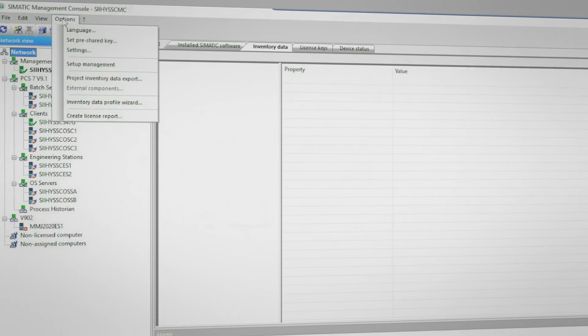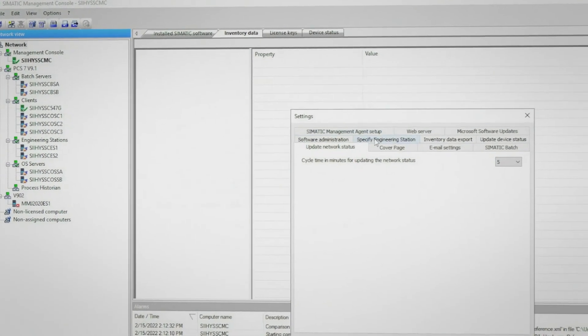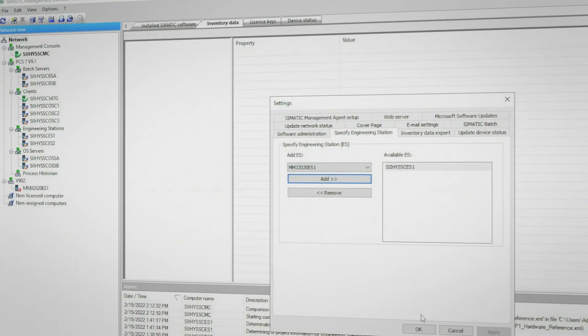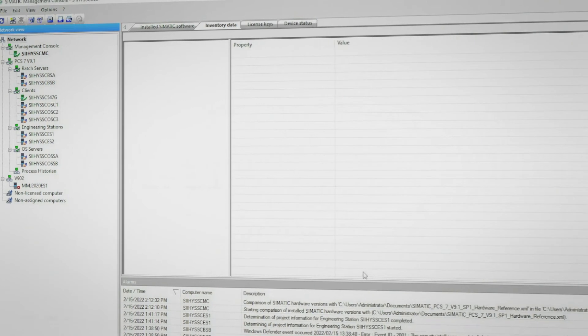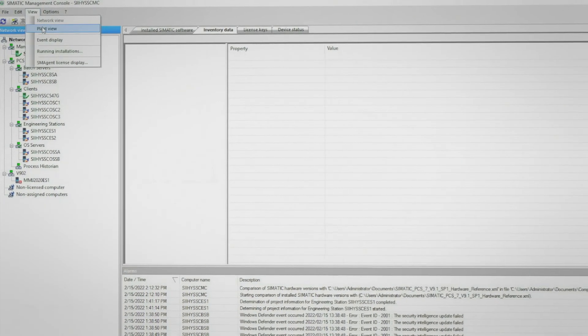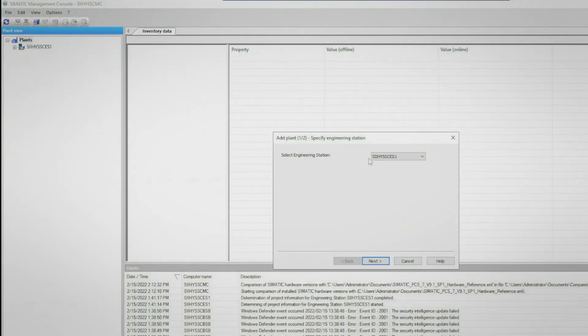Let's take a look at how to use the SIMATIC management console to do a hardware compare of our PCS7 system. In order to do this, we must first specify the engineering station where the PCS7 project is located. To do this, we go to Settings and then specify the engineering station. Now that we've done that, let's switch from the network view to the plant view of the management console. Here we can add a plant, select our engineering station, and then select the project where we want to compare hardware.